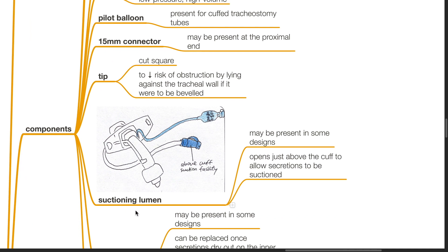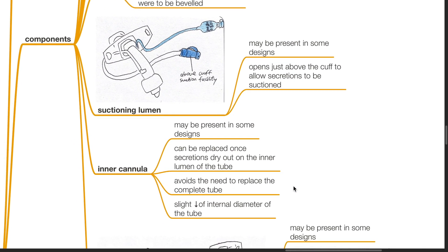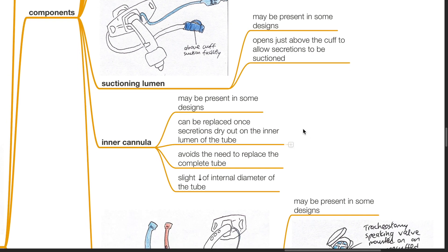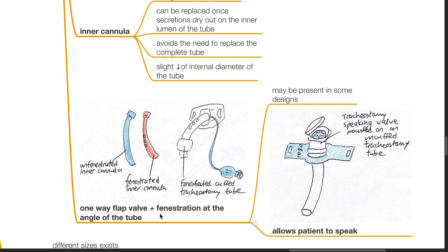The tip of the tracheostomy tube is cut square to reduce the risk of obstruction by lying against the tracheal wall if it were to be beveled. A suctioning lumen may be present in some designs, opening just above the cuff to allow secretions to be suctioned. An inner cannula may also be present, which can be replaced once secretions dry out on the inner lumen, avoiding the need to replace the complete tube, with a slight decrease in internal diameter. A one-way flap valve and fenestrations at the angle of the tube may be present in some designs and allows the patient to speak.